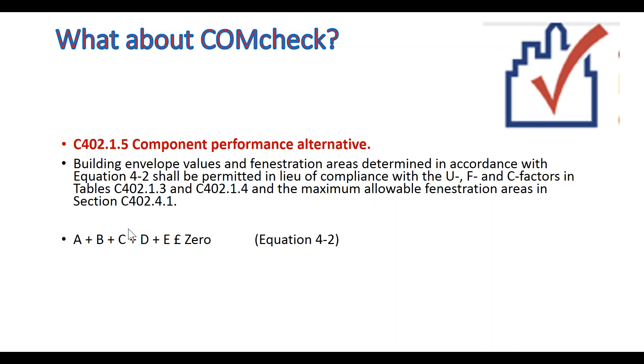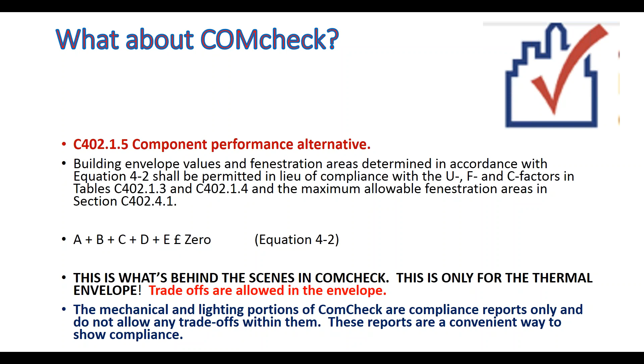So whatever you can convert to a U, F, and C factor can be traded off, just like in ResCheck. Keep in mind the trade-offs are only in the envelope. The mechanical and lighting are included in ComCheck, but they're just compliance reports - you can't trade within them. You can't do better lighting or better mechanical to get out of anything, and you can't get out of envelope by doing better in those other two. Those are just compliance reports; the trade, the checking account, is only in the envelope.